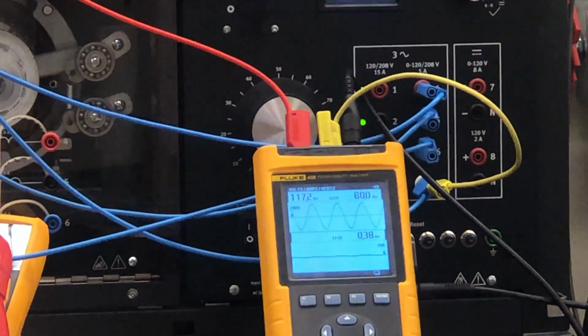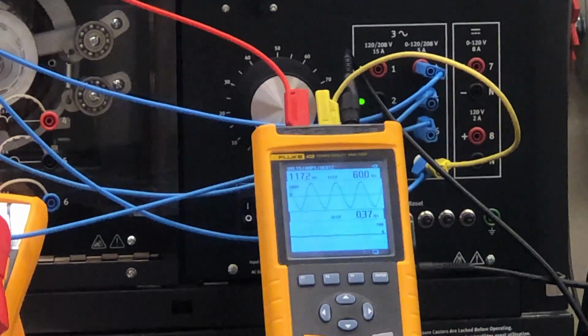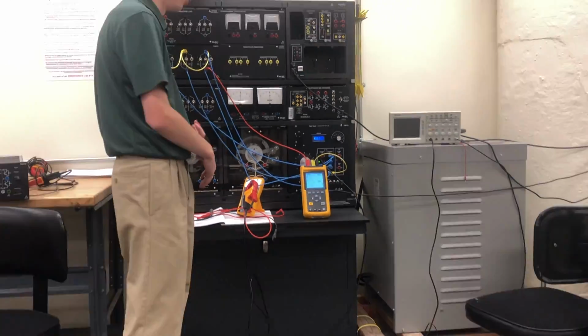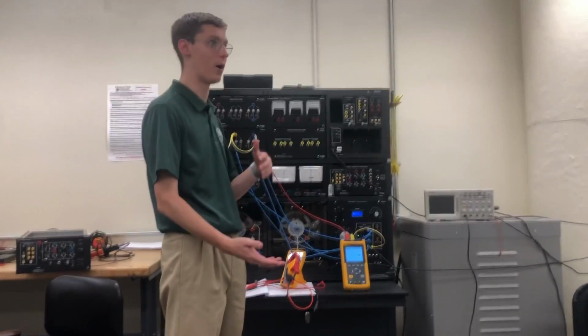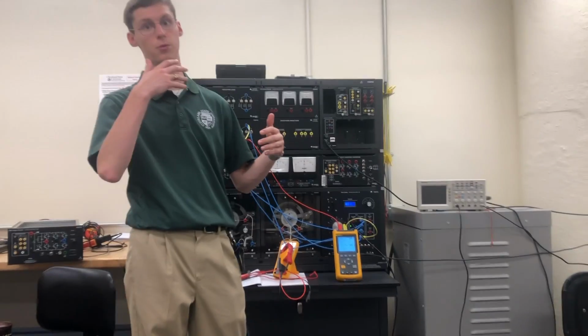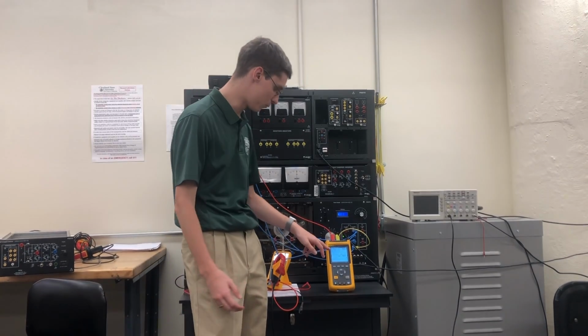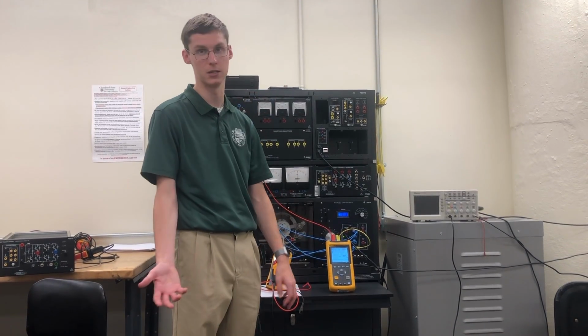And this is your line to neutral voltage. So be very careful when you're taking this that you are measuring exactly what you intend. If you're measuring phase voltage, reference it to the neutral. If you want line voltage, make sure you're referencing it to the appropriate line. Regardless, there's a waveform and a frequency display.